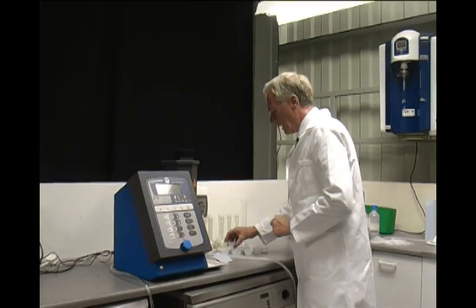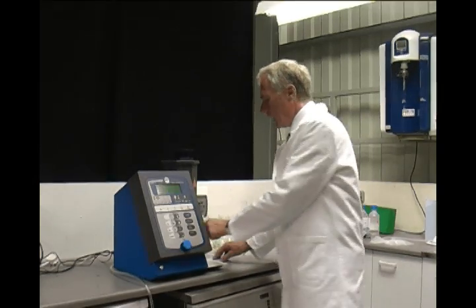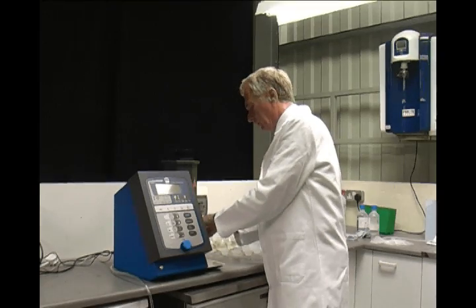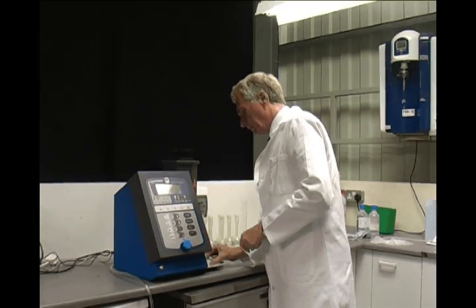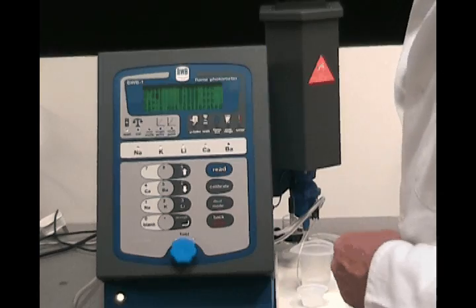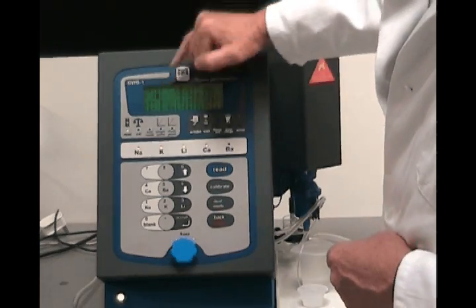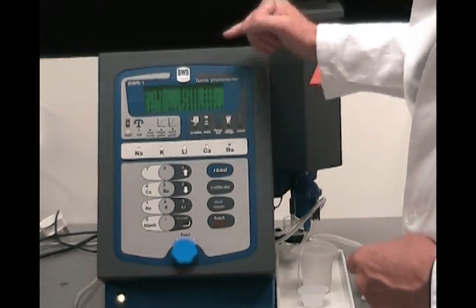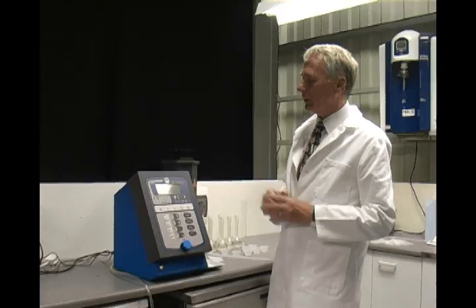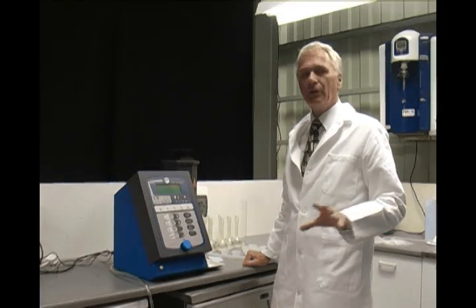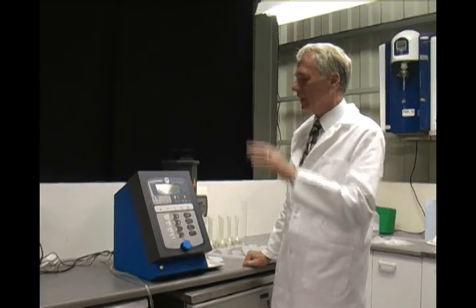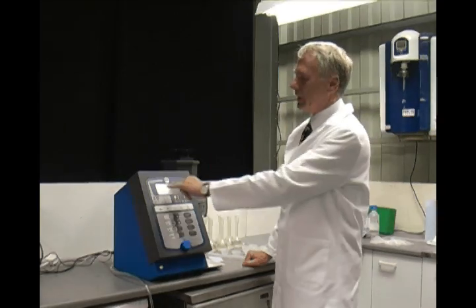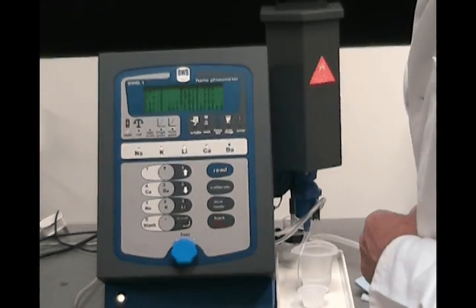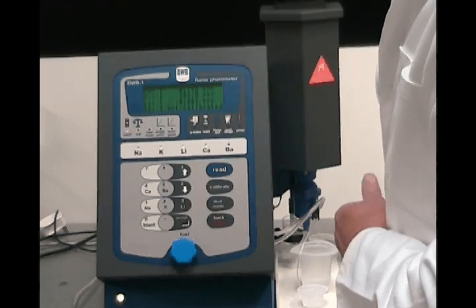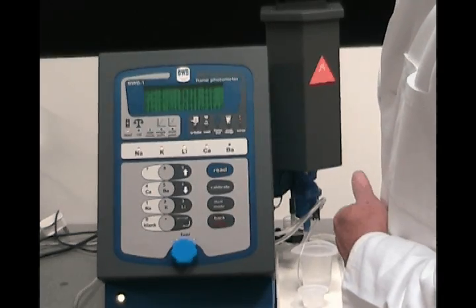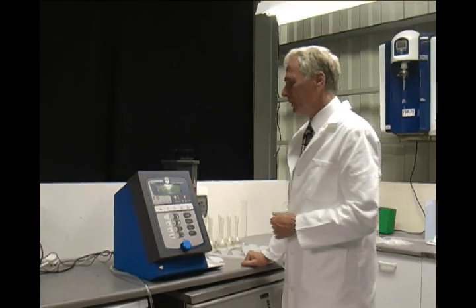I'll now do the same for a 100 ppm sample of potassium. You can see here we've got a big black dot where the noise is. This is because we've just injected a lot of chemical into the mixing chamber, and it is now starting to stabilise and coming back to a single dot in the middle. We've now got a nice stable reading, which is 101.6 ppm.